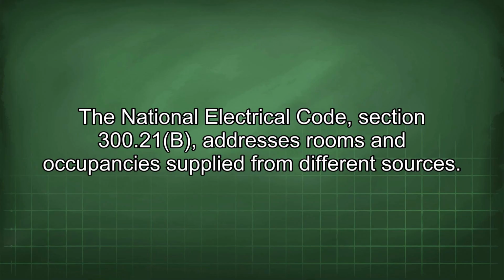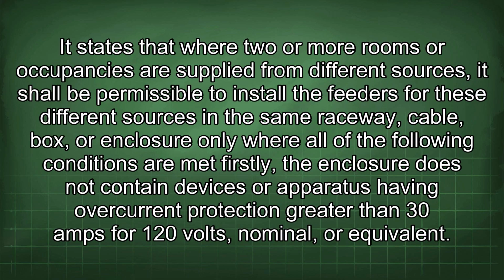The National Electrical Code, Section 300.21(B), addresses rooms and occupancies supplied from different sources. It states that where two or more rooms or occupancies are supplied from different sources, it shall be permissible to install the feeders for these different sources in the same raceway, cable, box, or enclosure only where all of the following conditions are met. Firstly, the enclosure does not contain devices or apparatus having overcurrent protection greater than 30 amps for 120 volts, nominal or equivalent.